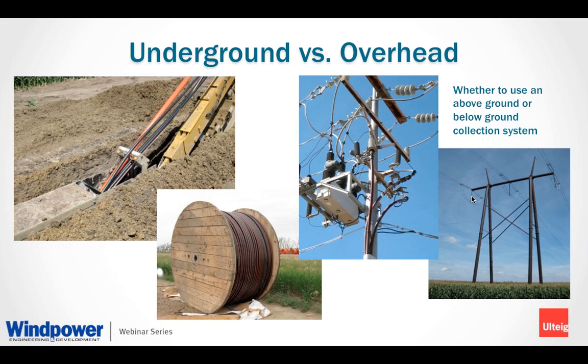So I'd like to start out with looking at the underground versus overhead option. Typically, a wind farm would have underground for the collection system, but I have seen it used as overhead. One of the benefits of having overhead is the conductors can actually take a lot more power flow than underground. This is simply due to they're suspended in the air and they have a lot more cooling effects versus having them insulated and buried under the ground, as heat is the biggest factor for how much power can flow through these conductors.